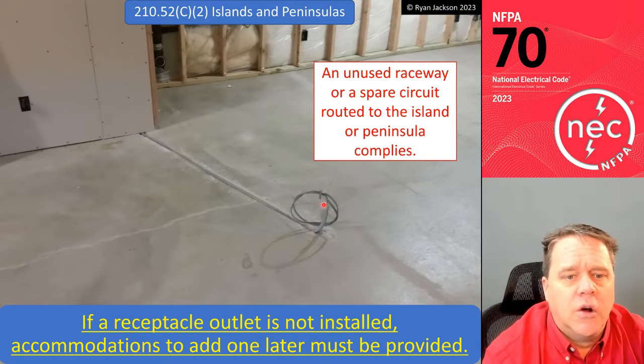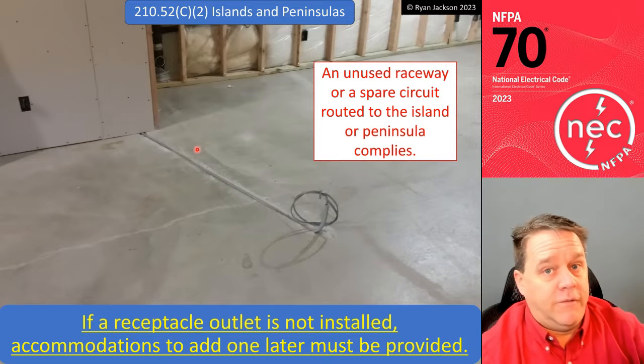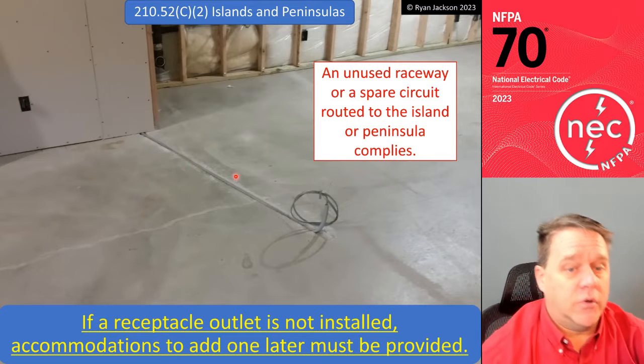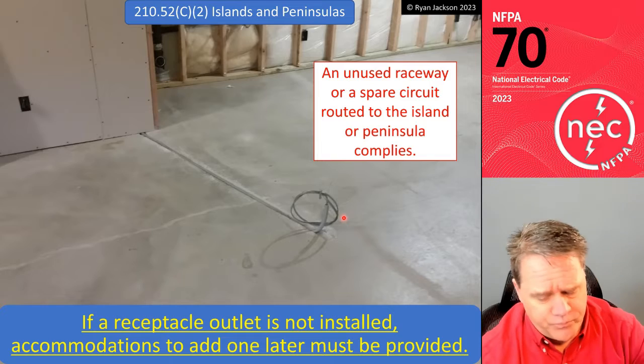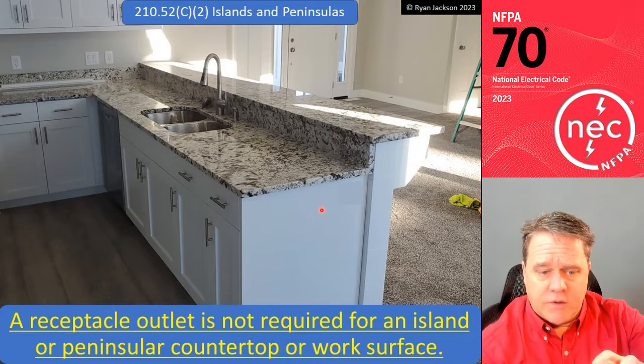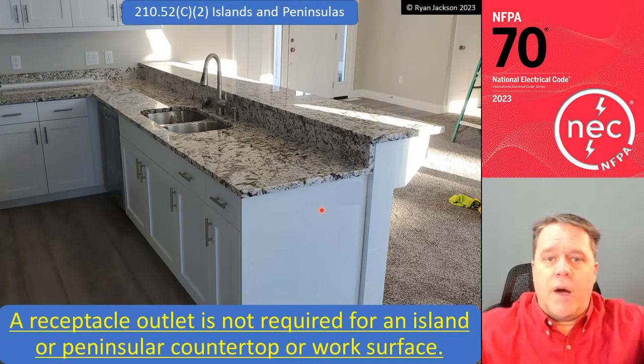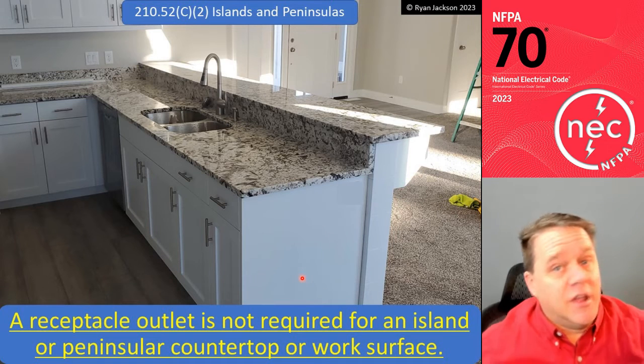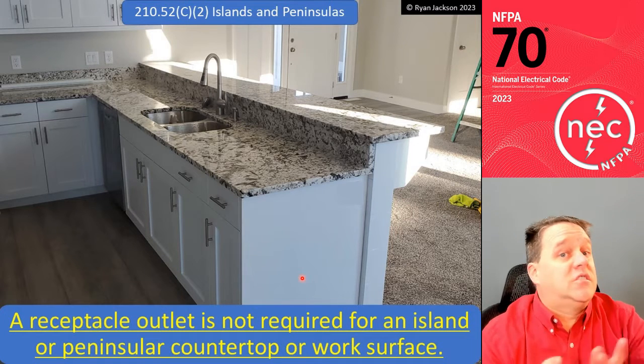All right, so run UF cable, or if you're in a dry location, if you're above ground, run NM cable, put it in a single gang box, put a blank cover over it, drop it in the bottom of the cabinets, and you're done. Right? Remember, that's still considered accessible.